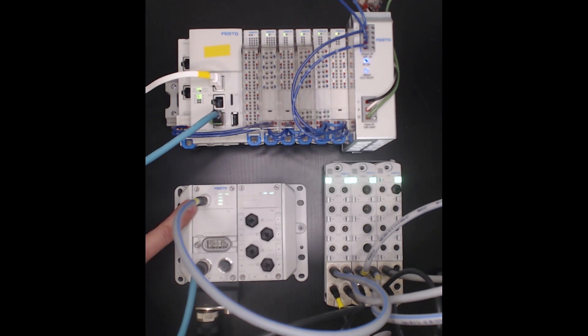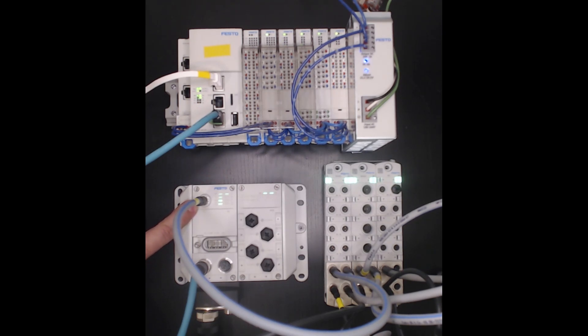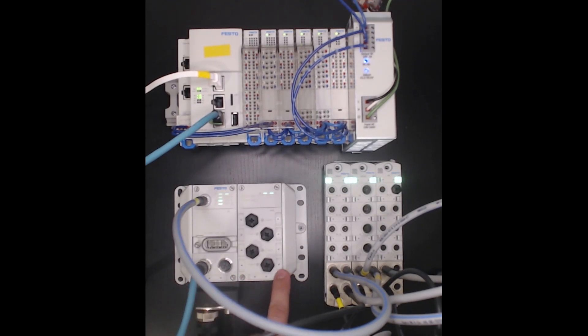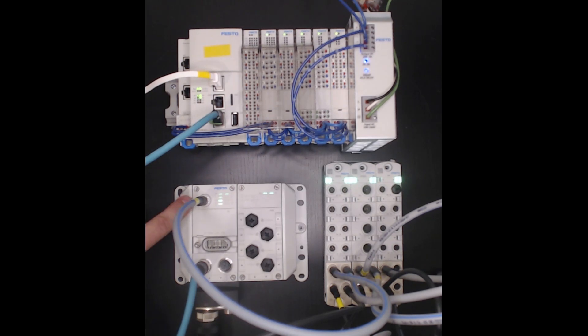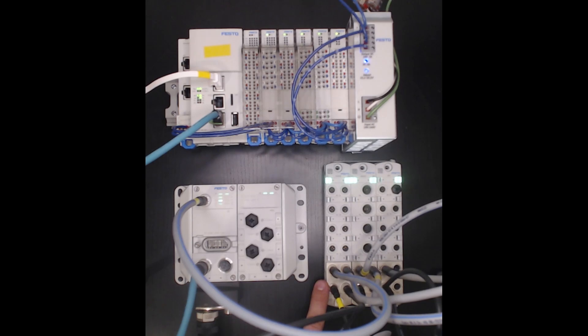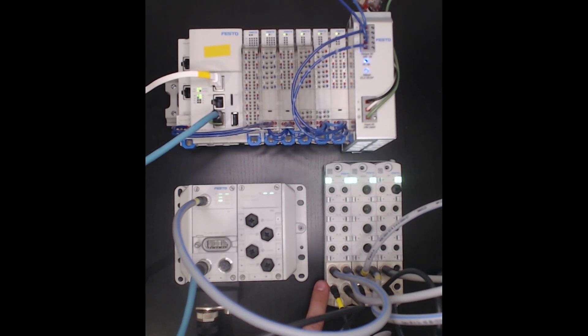On the top left of the APA field bus module, you can see I have a gray cable plugged in. This is the AP port. This allows me to expand the back plane of the CPX APA rack from these two modules out of the AP port over to my CPX-AP-I modules. You can see I have three modules here, a four DI, four DO, that's four digital in and four digital out module.